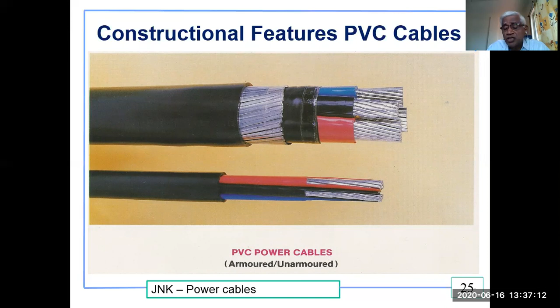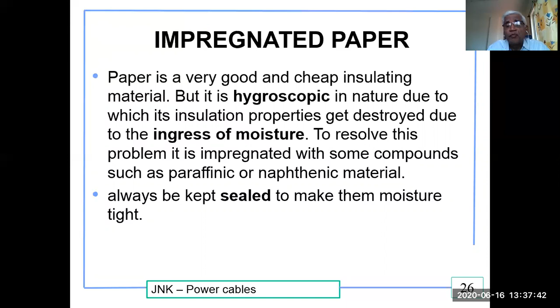Impregnated paper. Paper is a very good and cheap insulating material, but it is hygroscopic in nature. That means it absorbs the moisture, due to which the insulation properties get destroyed due to ingress of moisture. To resolve this problem, it is impregnated with some compounds such as paraffinic and naphthenic materials. It must always be kept sealed, moisture tight.